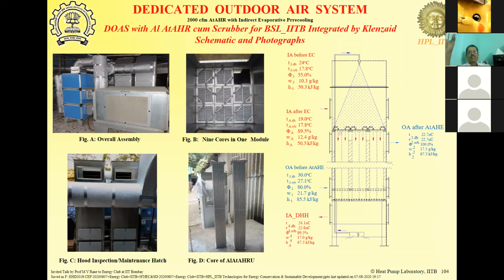So you should always check your design at the two extreme conditions. It need not satisfy 100% of your load at both extremes, but you should be aware of what it is capable of doing under those conditions, and then you decide your design point and design for that. Can you elaborate on this design point? Your extreme condition might be 45 or 48 degrees in your place. Are you aware of weather data from ASHRAE? I can get it, but I have not. Different temperatures are encountered with different frequency. If you talk about 48 degrees centigrade, it might happen only for maybe 30 hours in a whole year.